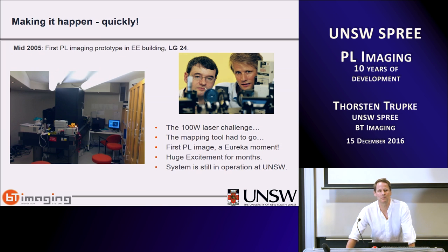And then we took our first PL images, and they were really eureka moments. It's hard to describe the excitement when you have a system that enables you to do a measurement that you previously took like several hours, and you then put a sample into that black box, you press a button, and half a second later you have a much better quality image. That was really exciting, and it was followed by months, if not years, of really exciting work here at UNSW and elsewhere. And that system is actually still in operation here at UNSW, just across the hall here in LG25.